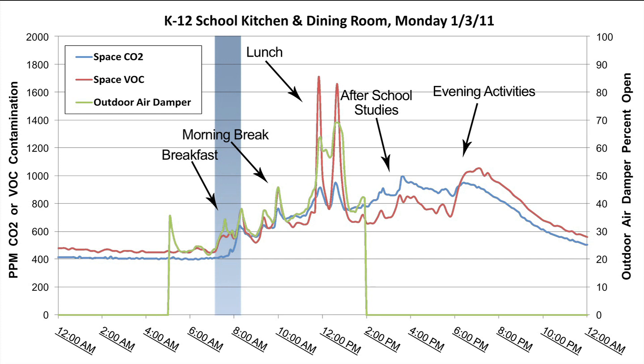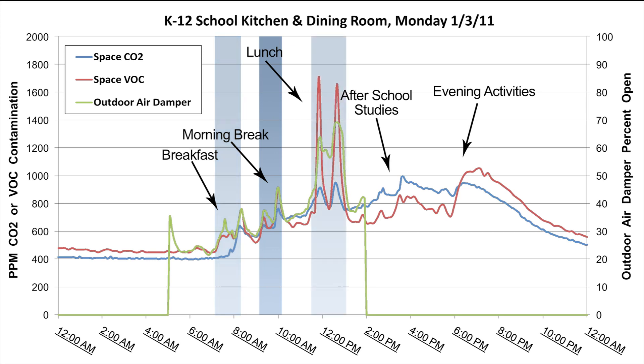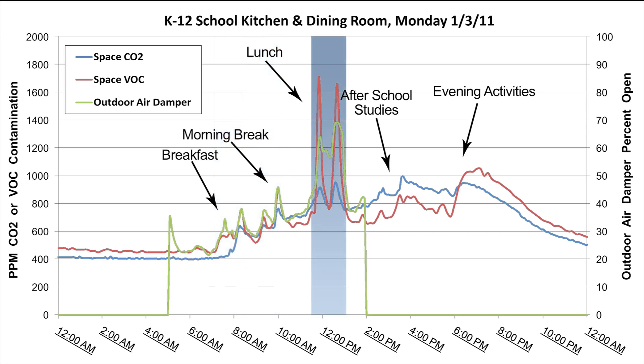At 7 a.m., the VOC sensor picks up the breakfast cooking aromas and activities. The CO2 sensor climbs a short time later as the students arrive to eat. The VOC sensor has slightly higher readings than the CO2 sensor during breakfast and the morning breaks because the VOCs from the food are added to the VOCs generated by the people. This is also seen at lunch, as cooking of the sausage pizza generated lots of VOCs which are added to the VOCs from the students and staff.